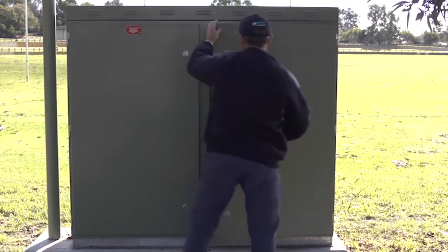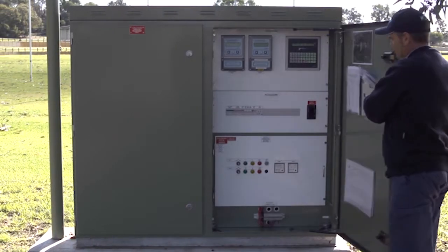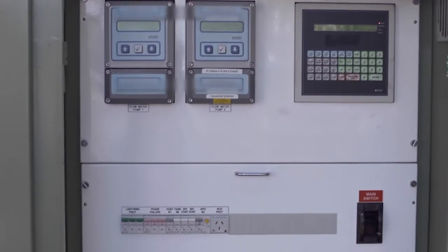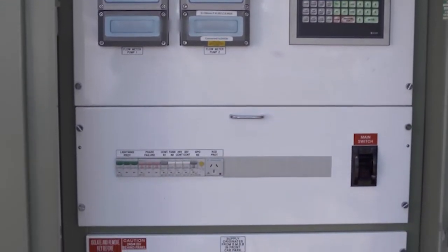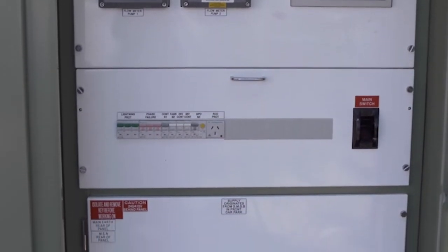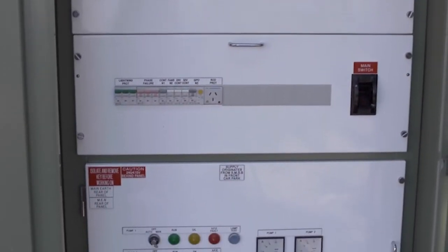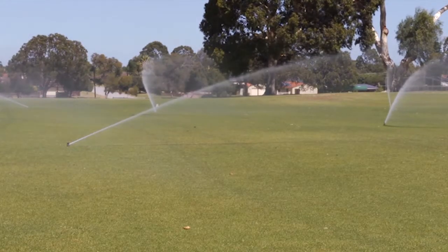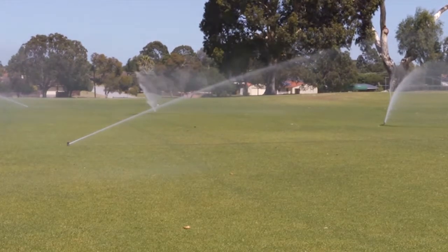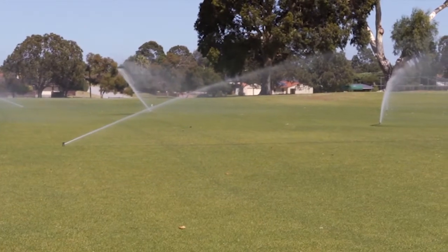Before proceeding with the assessment of the sprinkler layout, a quick run-through of the system should be carried out to make sure that the system is in good working order for the test. This doesn't mean that everything has to be perfect, but the system should be in the condition that it would normally be in when set for automatic cycles. This preliminary test could be conducted the day before the full assessment test.